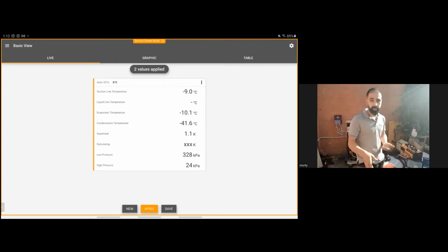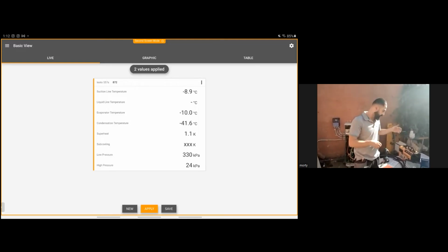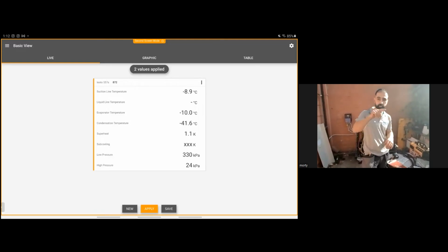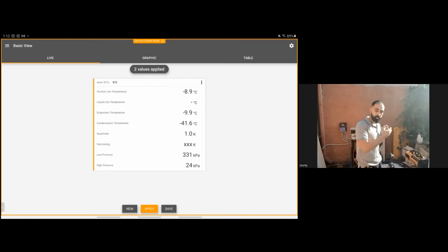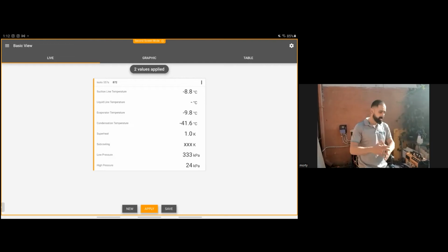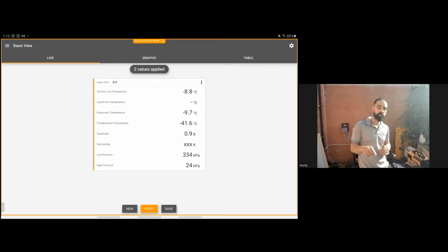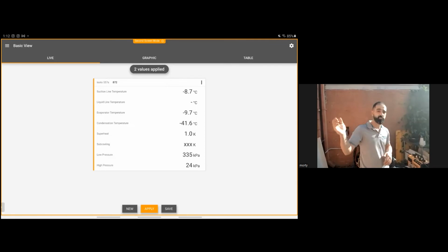So when you pull it completely down and you see the micron at 5,000 or 4,000, and you see the graph, if you've got a new instrument that has a graph, you'll see it spiking up and down. That's your moisture boiling off in the system, trying to exit, because pulling vacuum will start to separate the molecules between oxygen and hydrogen. Once you separate those two, they'll start to evaporate, and you'll see little spikes. And those spikes will be driven down, not upwards. If you turn off the vac and it sits there and keeps coming up in micron, that means you have slight moisture still in the system. You dump a bit of nitrogen in it, bring it up to atmospheric pressure, and pull vacuum again.